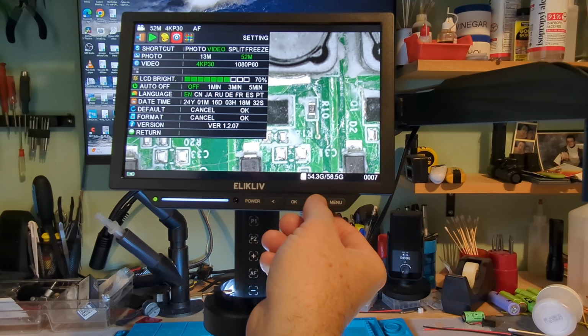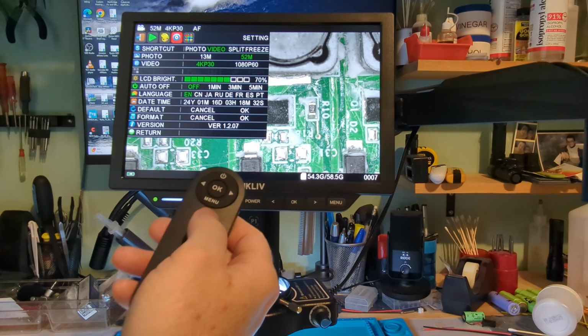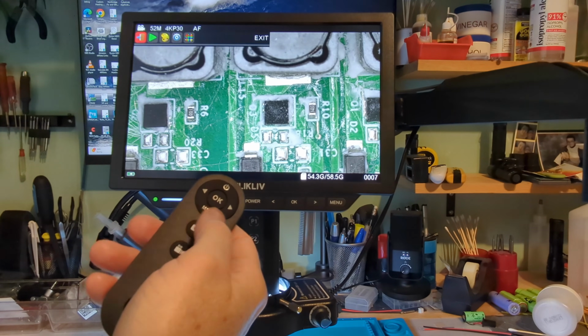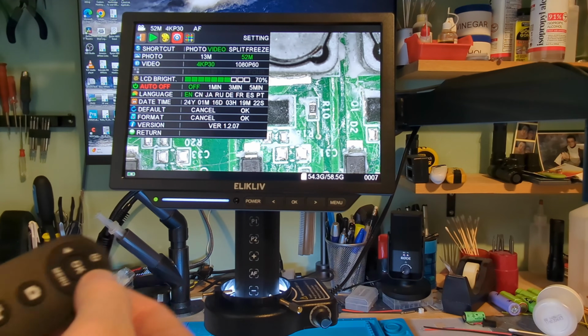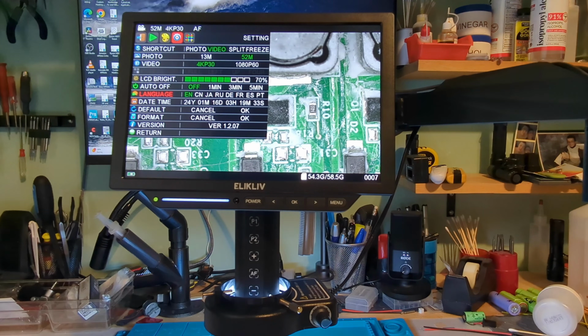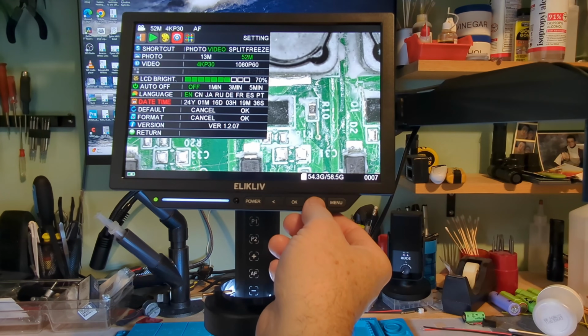We can return back and go to our settings. We can also use our remote to go in the menu and move it around. We just have to have it pointed directly at the microscope. In our settings, we have something like a shortcut. Do we want the OK button to be for photo, video, or split freeze? I have it on video. Our photo resolution, video resolution, LCD brightness, which I have turned up a little bit more than halfway, 70%, just to make sure it shows up good on camera for us. Auto off, language, date and time, back to default if you want to set the microscope back to factory default, format for the SD card, and it shows our version.